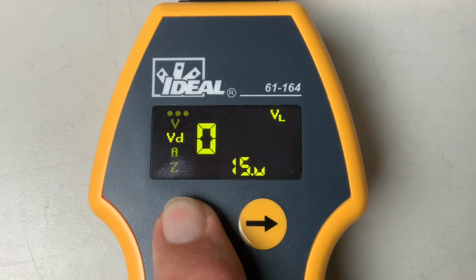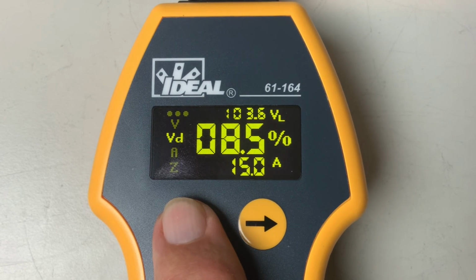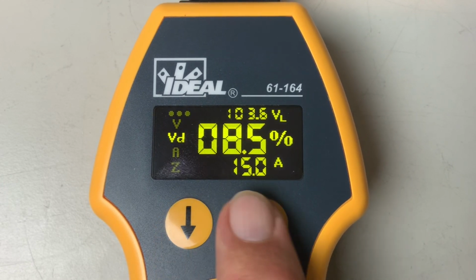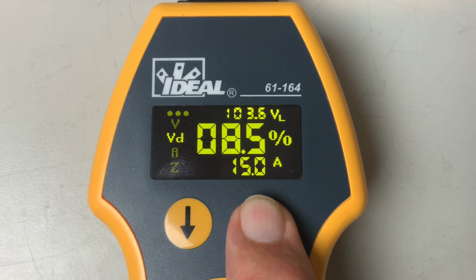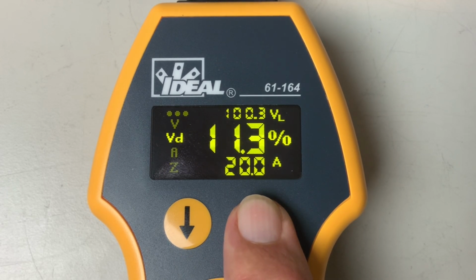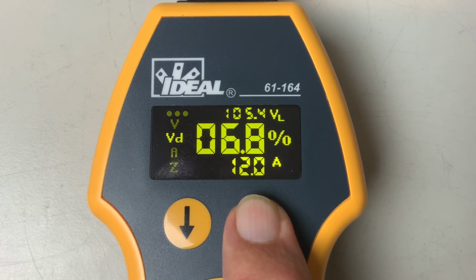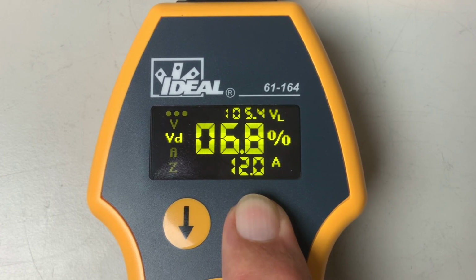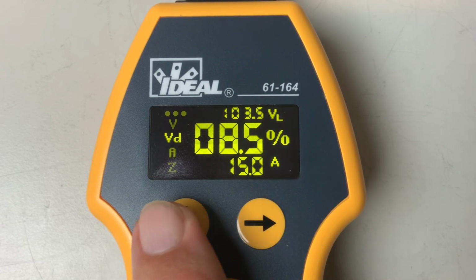The next screen is the voltage drop screen, which will tell you how much the voltage will drop at your outlet if you have high loads on it. Like if you have something drawing 15, 20, or 12 amps, it will tell you what percentage that voltage will drop on the wiring. Anything above 5% is supposed to be bad according to the National Electric Code. This was a pretty long wire, so you can see I've got some pretty heavy voltage drops here. And we'll talk about that a little bit more too.